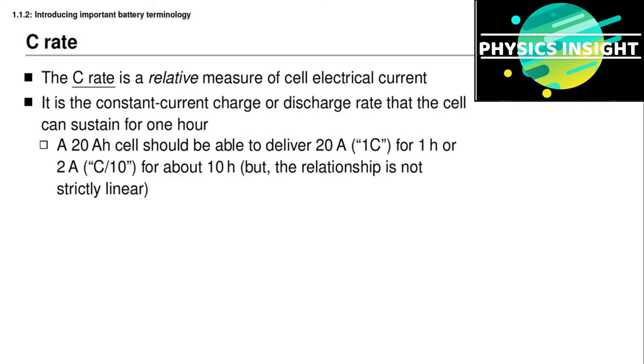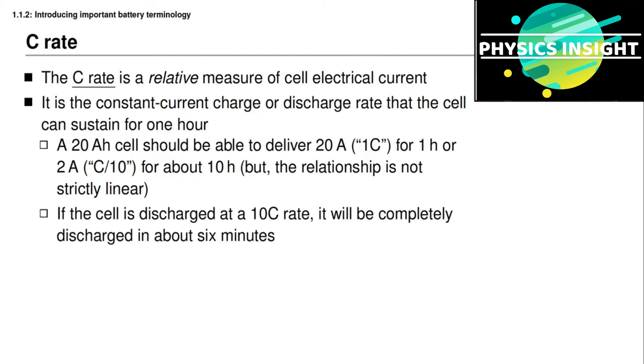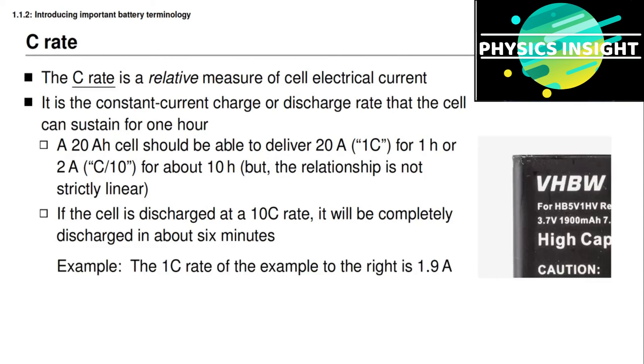To compute the C-rate from nominal capacity, simply write out the capacity with its units — for example, 20 Ah — then erase the H, leaving 20 A, or 20 amperes. So ampere-hours becomes amperes, and milliampere-hours becomes milliamperes. If we start with a fully charged battery cell and discharge at a 10C rate, the cell will be completely discharged in about 6 minutes. For the example cell with a nominal capacity of 1.9 ampere-hours, the 1C rate is 1.9 amperes, or equivalently 1,900 milliamperes.